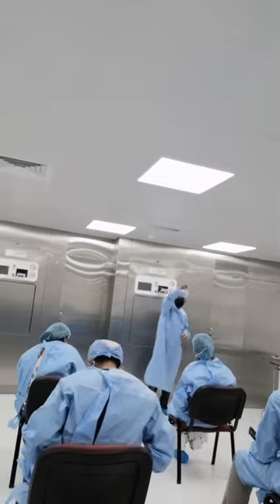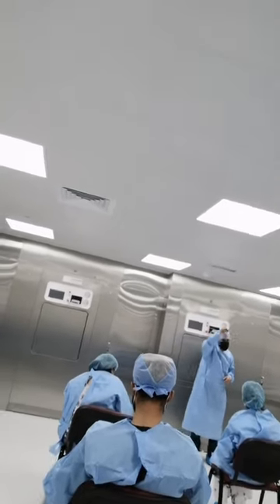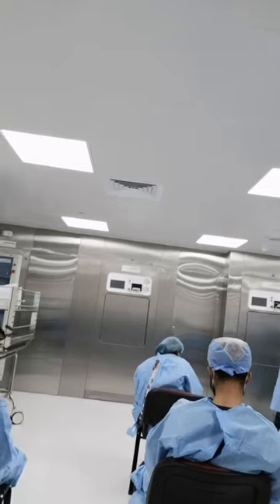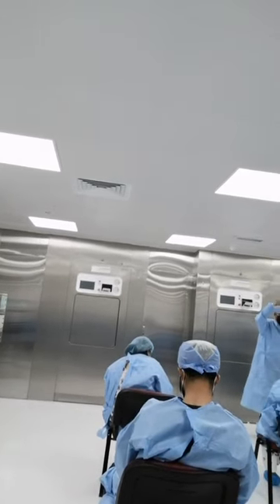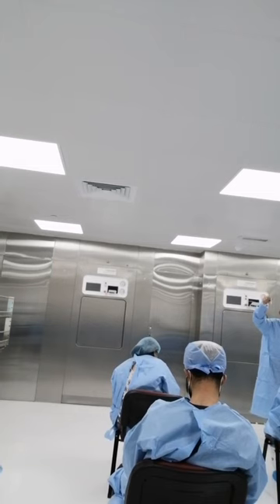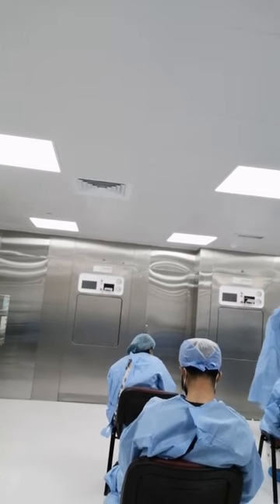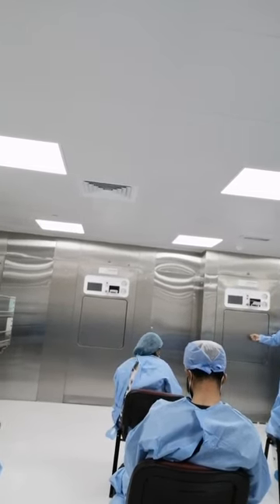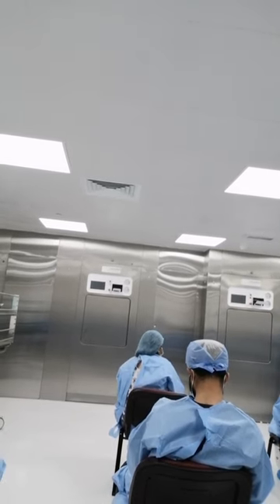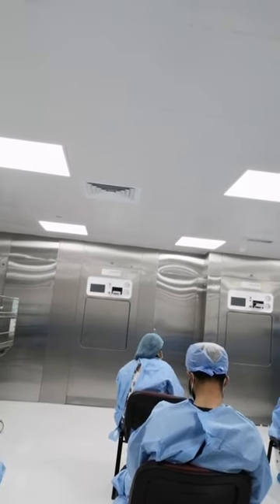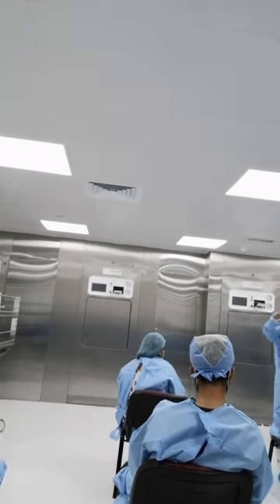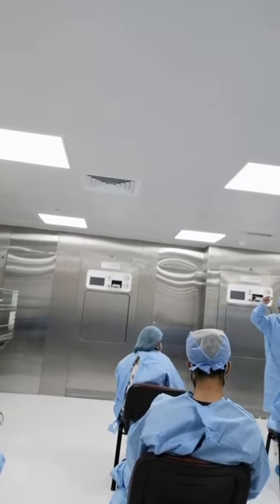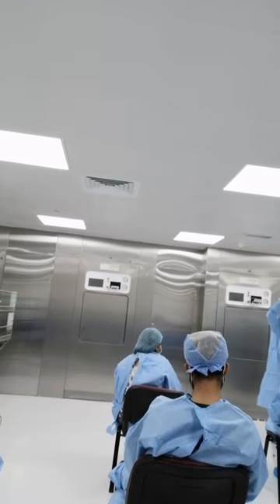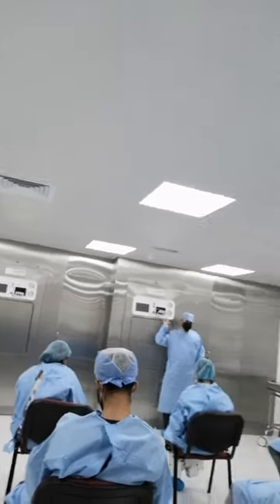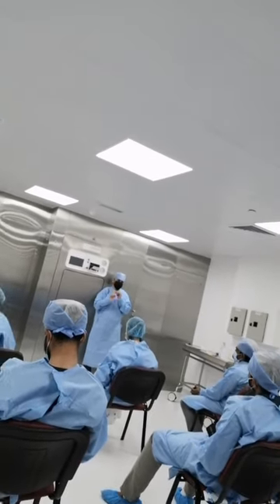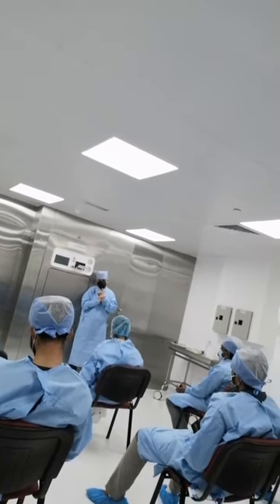So if this goes inside the machine, it must not change color, or it must not give any indication on the biological indicator or biological reader that there is any kind of biological growth. Because if there is biological growth, then this machine didn't kill spores. Because if it kills spores here, it will kill spores on the instruments. If it doesn't kill spores here, it will not kill spores on your instruments. And this is the third test you do as CSSD on this paper. So it's chemical indicator, biological indicator, and Bowie-Dick test.